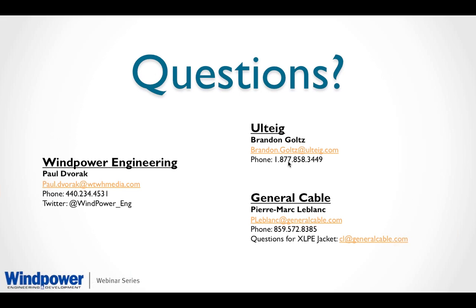I have a question for you, Brandon. In one of your earlier slides, you showed some transformers, I think a series of 3, and one of them was an oil-filled transformer. They require some maintenance. What kind of maintenance does an oil-filled transformer require? Well, typically an oil-filled transformer will have dissolved gases within the insulating oil throughout its lifespan. These dissolved gases change the properties of the oil, and maintenance crews will go out, normally annually, and test it. There's a specific test to check the oil and make sure it's still in proper working order. Sometimes they also have to fill it up if it's leaking. I see. That could be problematic.